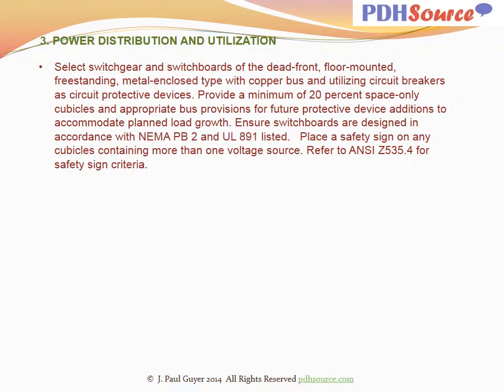Select switchgear and switchboards of the dead front floor-mounted freestanding metal enclosed type with copper bus and utilizing circuit breakers as circuit protective devices. Provide a minimum of 20% space only cubicles and appropriate bus provisions for future protective device additions to accommodate planned load growth. Ensure switchboards are designed in accordance with NEMA PB2 and UL 891 listed. Place a safety sign on any cubicles containing more than one voltage source. Refer to ANSI Z535.4 for safety sign criteria.